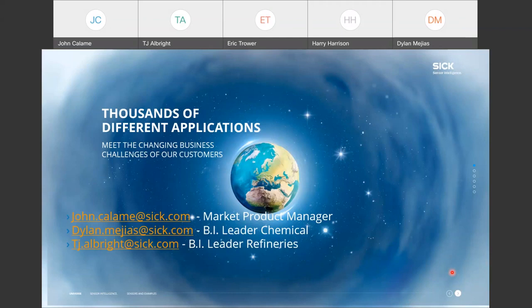Yeah, so I can answer that one. The accuracy is going to be very application dependent. Usually it's going to be 2% or less is what we're going to shoot for. And when the application questionnaire gets filled out, we will go through and pick the proper length of the probe, proper measuring path, and everything to fit the needs of the application to meet that accuracy. Like I touched briefly earlier on the GM32, it has two different versions of measuring.